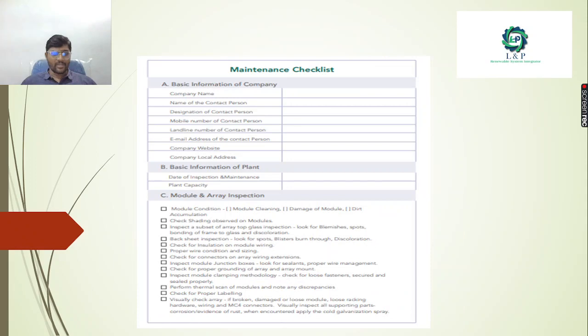And grounding considerations. In the maintenance checklist, make sure it includes the company name doing the maintenance process, its number, its mail ID, and the company website. When you're doing the inspection, note the plant capacity and what things you have inspected on the module and the array side. Make sure it is cleaned properly and there are no damages. If you notice any damage, mention it in the report. Do the proper cleaning process.